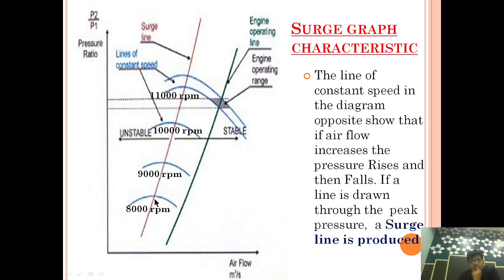So if we put a dot at each of the peak points — of the 8,000 RPM, 9,000 RPM, 10,000 RPM line, and so on — and connect those dots, we get a line. This line is called the surge line. As I have written: if a line is drawn through the peak pressure of each constant speed line, that line is called the surge line.